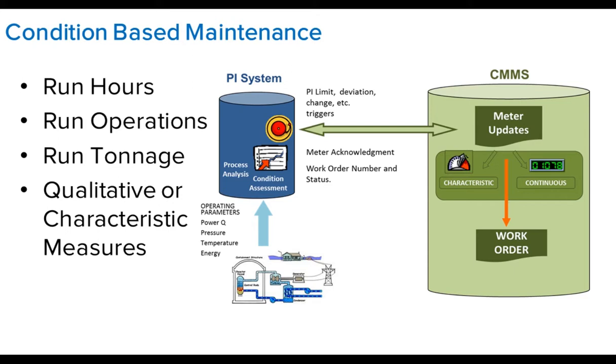In this case, we're taking information about the asset, typically usage-based information, things that come frequently, say maybe a 1, 4, or 15-second rate, sending this data into a condition-based management system, a centralized maintenance management system. If we sent this data directly to a CMMS, it would overwhelm it. That's why you use an operational database like Pi that can take those various frequency rates of fast real-time data and put it into an area where it's ready and put together.